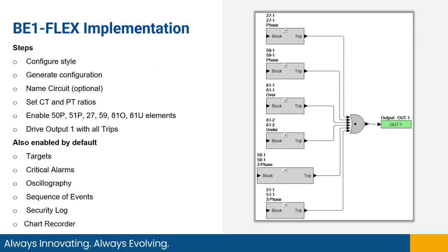So we'll go through the example. Again, you configure the style like I did. Generate the configuration with the auto generate. Name the circuit. Put in the CT and PT ratios. Enable and create those elements and put in the settings and drive the outputs.